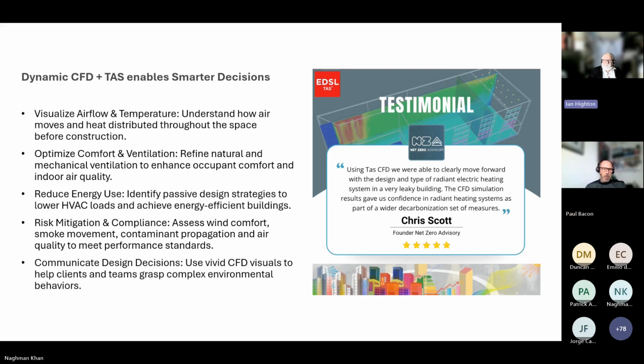Yeah, and it was an interesting design because it wasn't just about infiltration CFD. They had some very interesting, I think, battery stuff, PV stuff, and did they eventually get to be carbon neutral? I mean, was it zero? Well, yeah, we put enough PV on the building in the end to get it down to carbon neutral, but the actual energy dropped significantly just by changing the heating systems from the work we did. Okay, yeah, that makes sense.